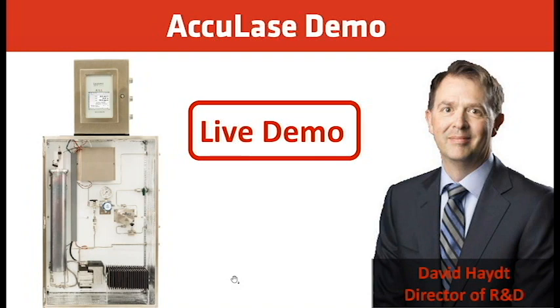Okay. The sample pressure, is that PSIA or PSIG? So the input sample pressure is 10 PSIA, and then the cell itself operates at about, or pardon me, I'll back up. The input pressure to the analyzer is 10 PSIG, so that's gauge pressure. Once it goes through the metering valve and then is drawn out with the pump, the balance between that flow and pump pressure draws the pressure inside the cell down to about 3 PSIA.